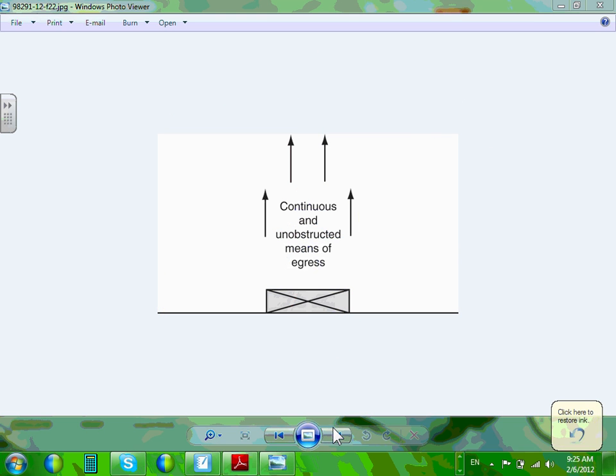The minute that Nick and the architects decide to orient this switch gear here, now you have to have another entrance here. See, it goes by the orientation. If you want one entrance, make sure you put the door right opposite the equipment. You orient the equipment here, then you have to have another entrance, or double the clearing distance. Any question, guys, about the space in front of the equipment? Okay, so they're unobstructed. These are a big deal, guys, especially for us designers.